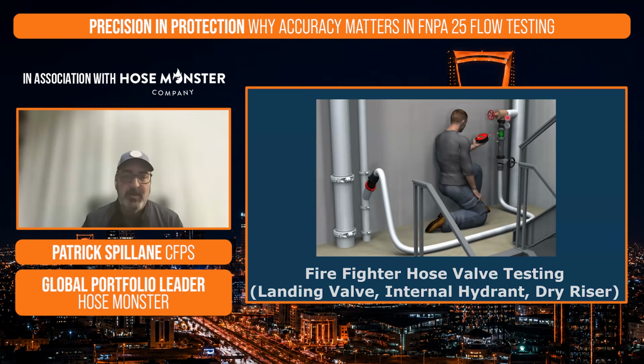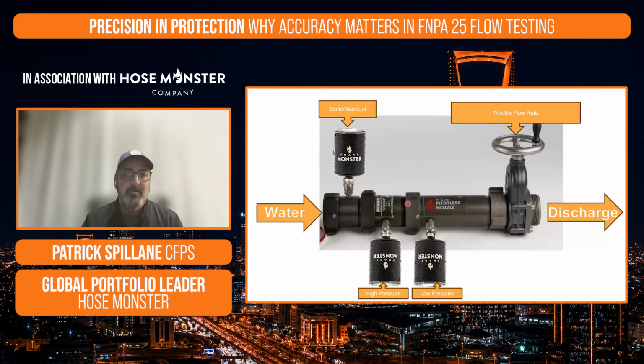Here we have our inline Pitotless Nozzle kit. So this uses our Pitotless Nozzle technology, and we basically turn this into a Venturi flow meter, a portable Venturi flow meter. So now we can hook this up to any standpipe landing valve connection, fully charge our units. We can document our static and residual pressures. If it's a PRV valve, right? If that PRV is working, we're going to be able to document that with our static residual pressure check. And then our smart monitors can be installed there to get our high and our low pressure reading.